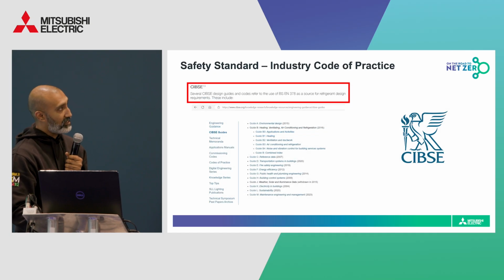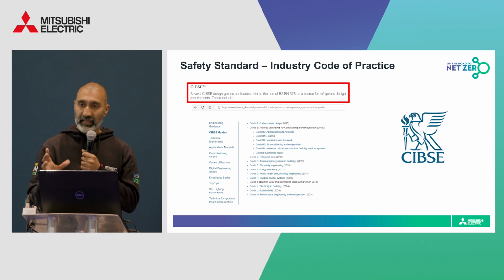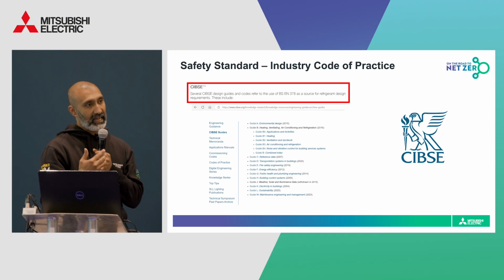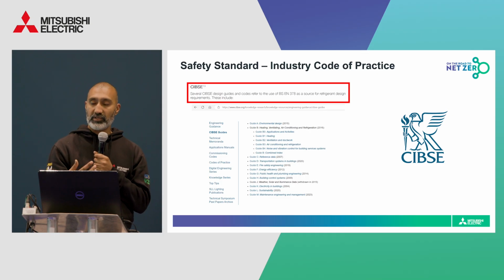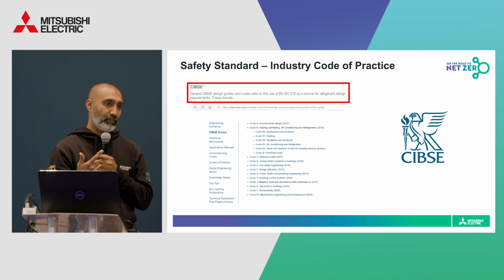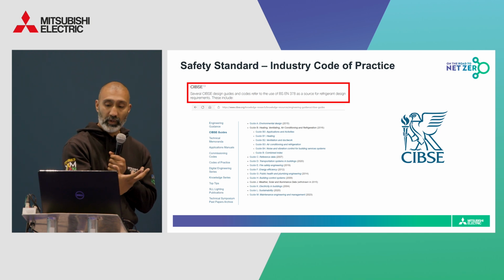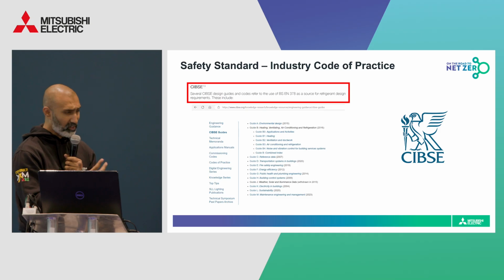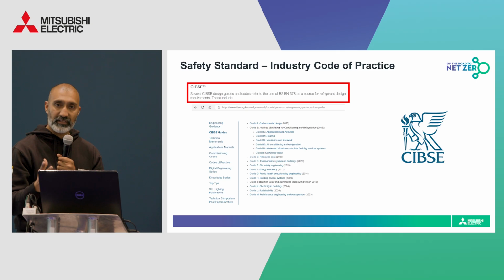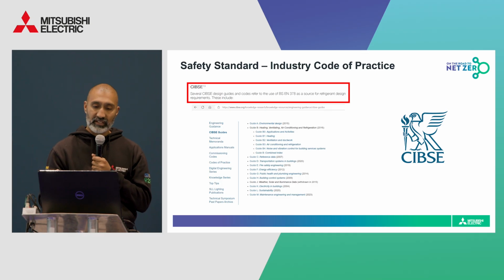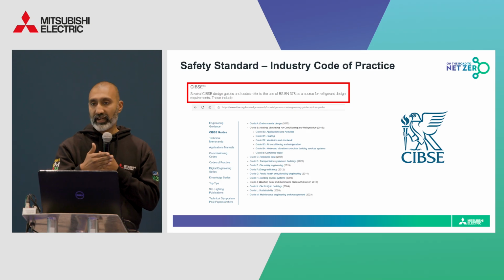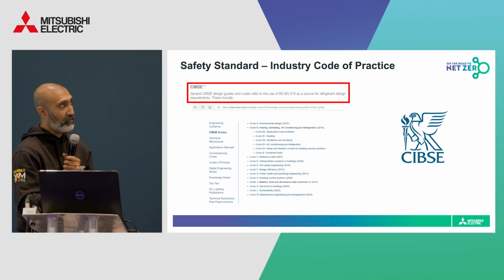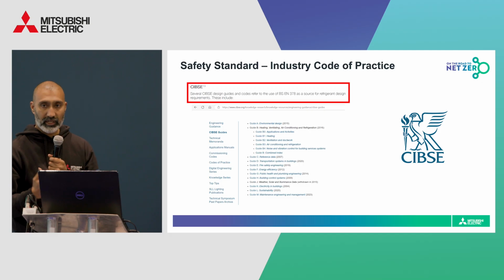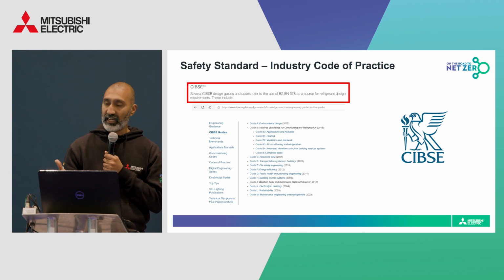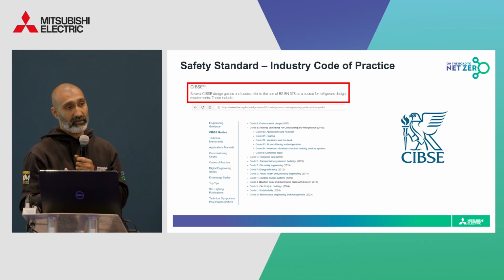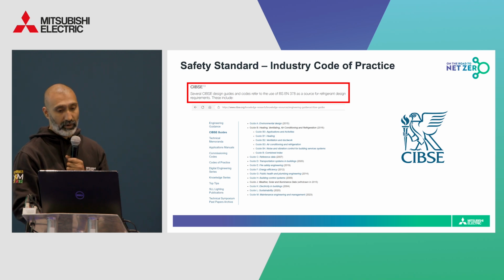Both horizontal and vertical standards address safety, which can be kind of confusing, especially with A2L refrigerant systems. And the decision is becoming increasingly more important due to the updated building regs and the updated Building Safety Act from 2022, which introduces new safety responsibilities throughout the supply chain. So construction professionals can refer to a whole bunch of different guidance from industry associations, regulations, and organizations to determine which recommendations to follow and how to apply them. However, Part F of the building regulations, BREEAM new construction, REFCOM, the IOR, and a whole bunch of CIBSE design guides and codes all actually refer to the use of BS EN 378 as a source for refrigerant design requirements.